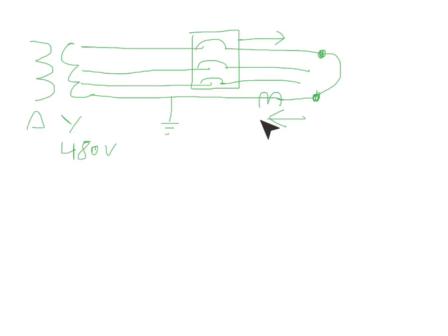Okay, now if the breaker does trip, you're going to want to check that, obviously, you have the ground fault enabled on the circuit breaker to the right setting level, whatever you're testing at. The most important thing is to check the polarity of the CT. You can figure out rather quickly that the CT polarity is incorrect because it'll do a half trip. So say you have the ground fault here set at 250 and it trips at 125 amps. The reason it trips at 125 amps is because it's seeing 125 amps coming this way, and it's seeing 125 instead of coming back this way. If the polarity is incorrect, it'll see it going that way, so it'll add it. That's why you'll get half a trip.